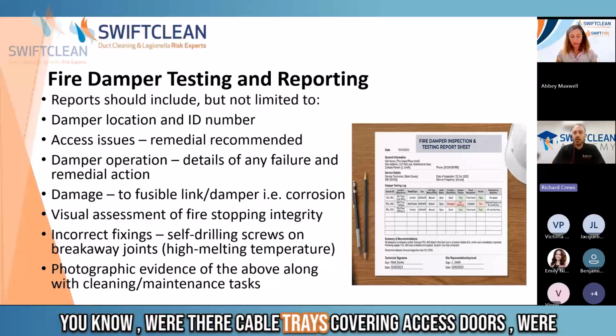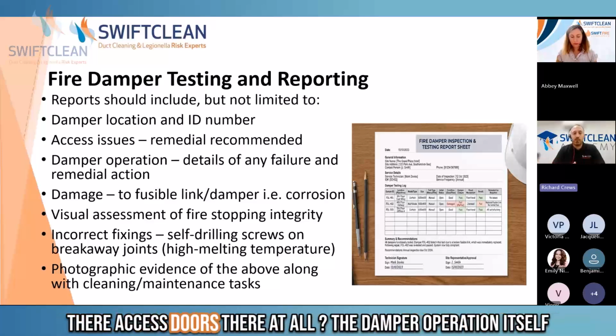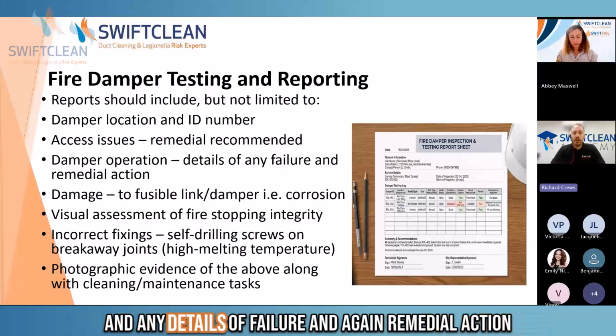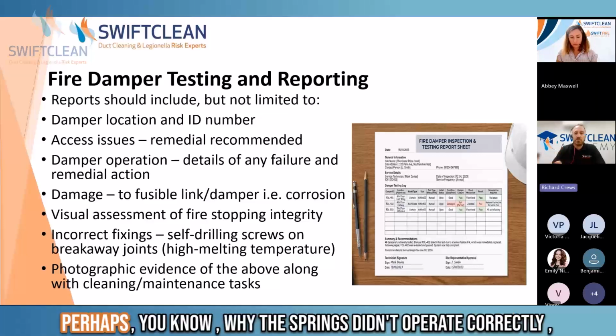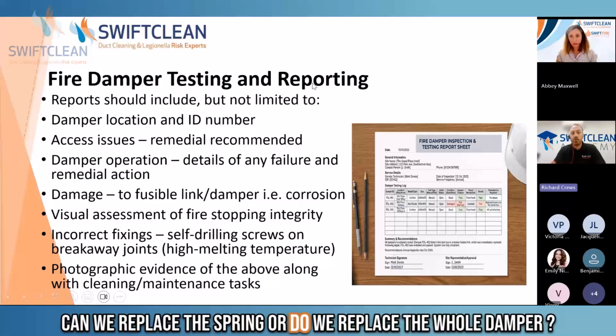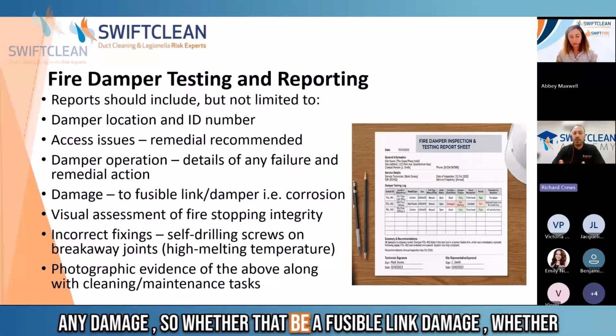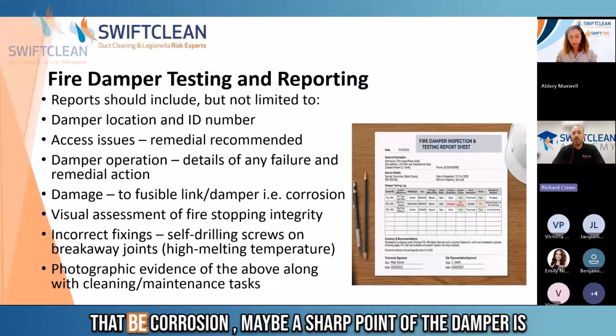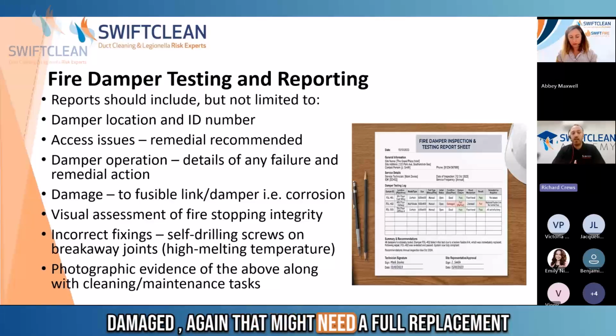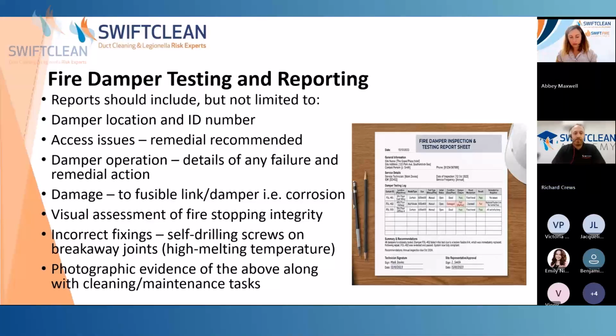Were there cable trays covering access doors? Were there access doors there at all? The damper operation itself and any details of failure, and again, remedial action. Perhaps one of the springs didn't operate correctly. Can we replace the spring, or do we replace the whole damper? Any damage, whether that be fusible link damage, whether that be corrosion, maybe a sharp point of the damper is damaged, again, that might need a full replacement.